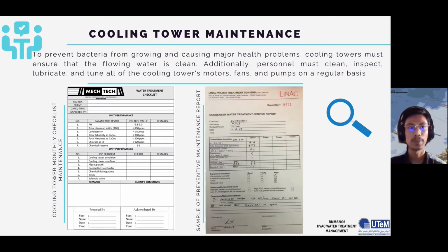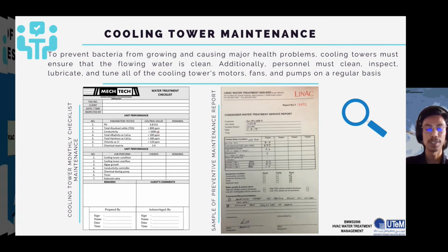Okay, next, cooling tower maintenance is to prevent bacteria from growing and causing a major health problem. Cooling towers must ensure that the flowing water is clean. Additionally, personnel must clean, inspect, lubricate, and tune all of the cooling tower motors, fans, and pumps on a regular basis. Okay, this is a sample cooling tower maintenance checklist and a sample preventive maintenance report.